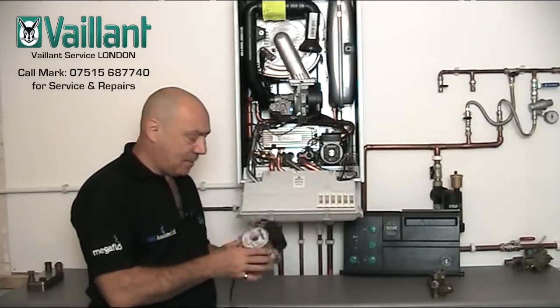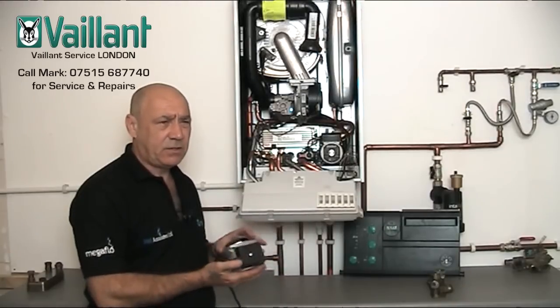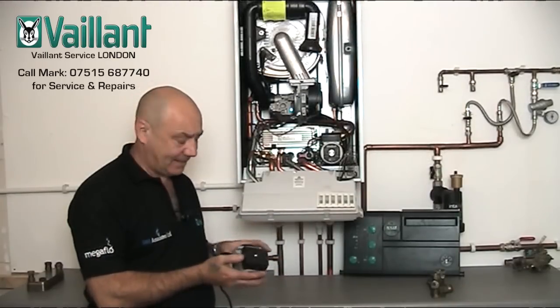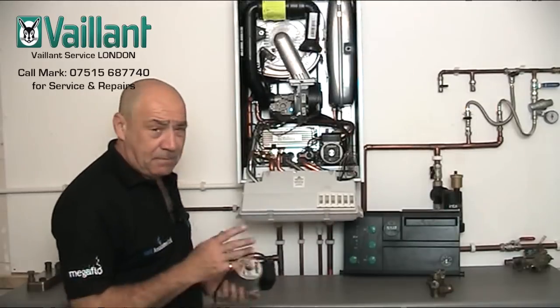We're just going to have a quick chat about Vaillant pumps on the Vaillant Ecotec. Now this doesn't apply to any boiler that's probably manufactured after sort of 2007, 2008, 2009 maybe. But the earlier versions had massive problems with pumps.